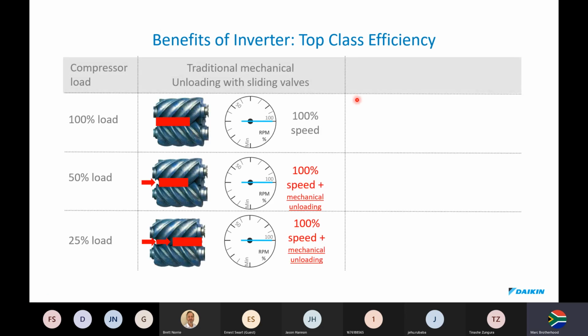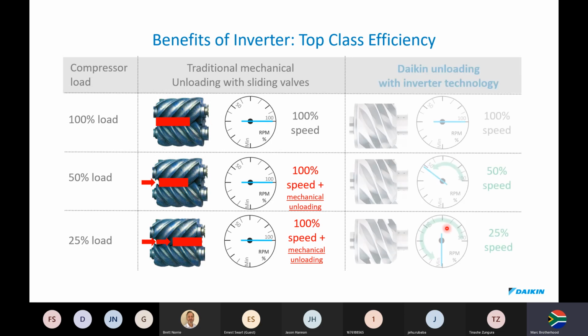Well, if we look at a conventional chiller, a double screw, you will see that at 100% capacity, 50% capacity and 25% capacity, there's no variation. All you're doing is altering the geometry of the compression area. However, the compressor motor, the rotor, is still spinning at maximum RPM. We're not modulating the speed that the rotor is spinning at. So these things spin at a set speed. We just alter the compression cycle using a mechanical slide control.